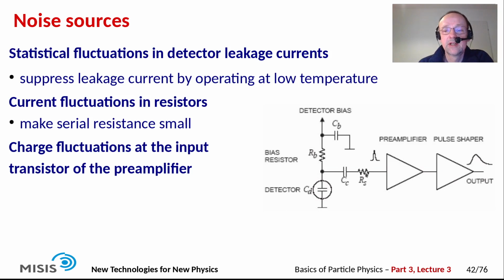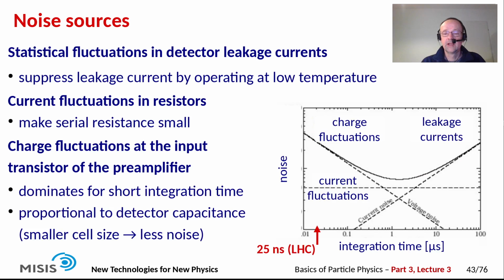Another very important source of noise is charge fluctuations at the input transistor of the preamplifier. And this noise is proportional to the capacitance of the detector that we connect to the amplifier. Now, this dominates for short integration time. So we see in this plot here the different noise contributions as a function of the integration time of the amplifier. And at the LHC we are at something like 25 nanoseconds here, so in the range where charge fluctuations, which are proportional to the detector capacitance, dominate completely.